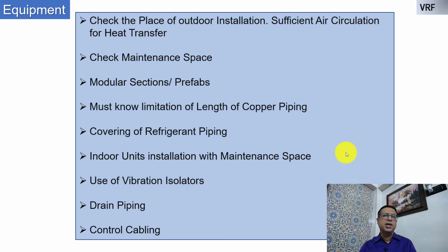And most importantly in VRF is the communication cabling, the control cabling. If this goes wrong, your system gets into problems and you will face a lot of trouble. I have faced many problems in my experience. The control cabling needs to be proper, and the continuity needs to be checked properly. Otherwise, if you have a communication error, your systems will not work. So these are some of the aspects for VRF.